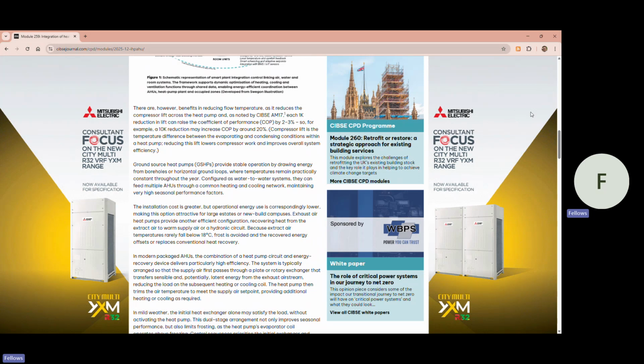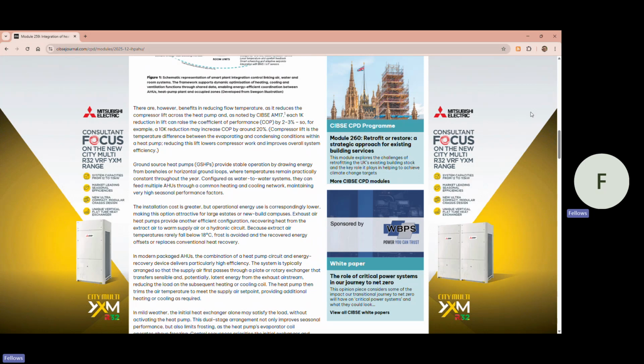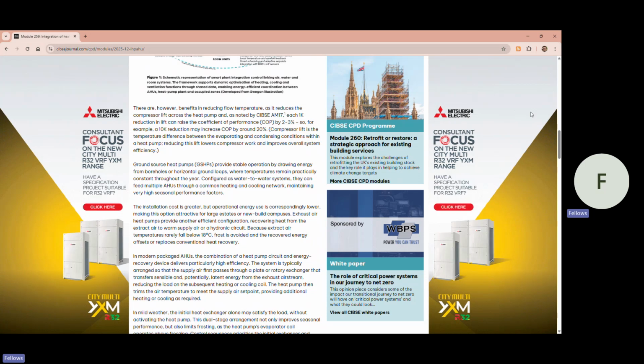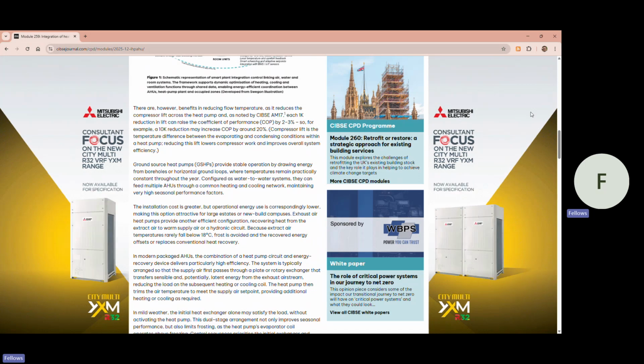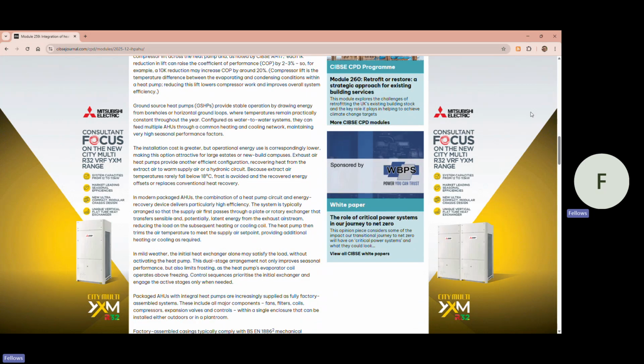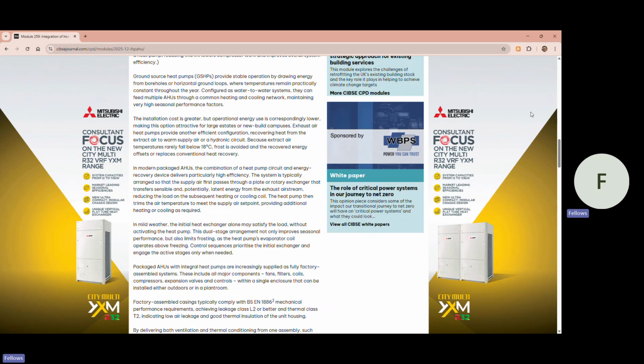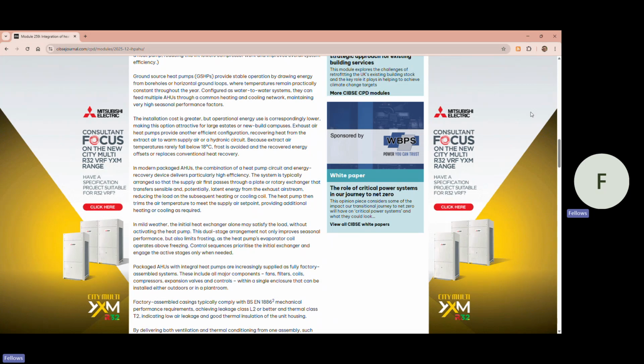Exhaust air heat pumps provide another efficient configuration, recovering heat from the extract air to warm supply air or hydronic circuit. Because extract air temperatures rarely fall below 18 degrees C, frost is avoided, and the recovered energy offsets or replaces conventional heat recovery. In modern packaged AHUs, the combination of a heat pump circuit and an energy recovery device delivers particularly high efficiency.